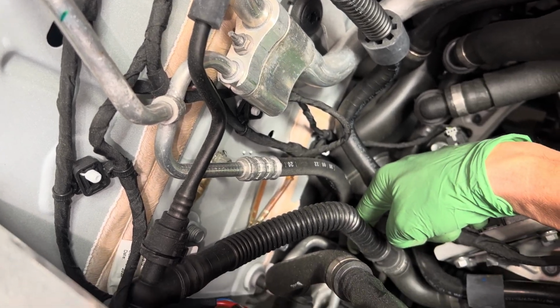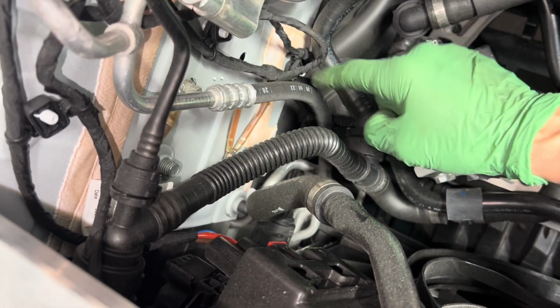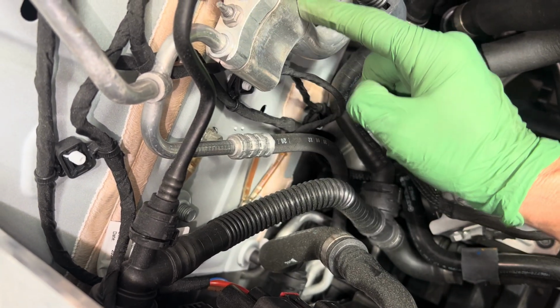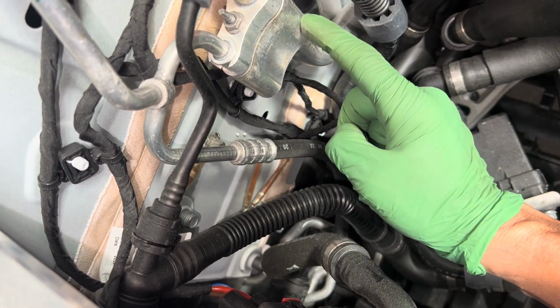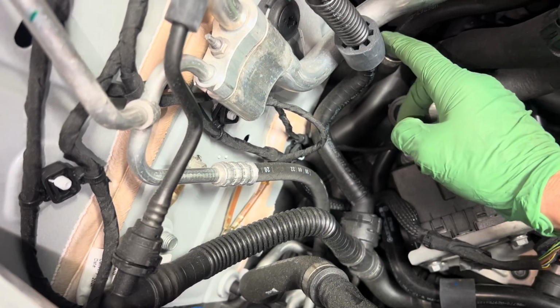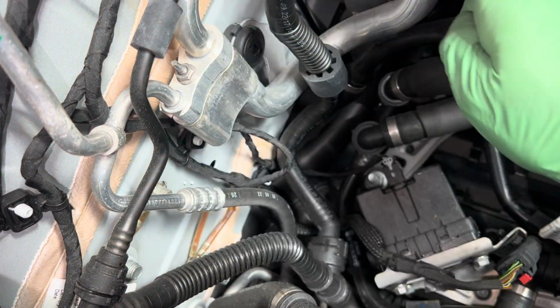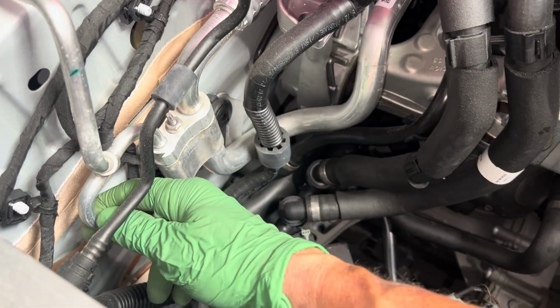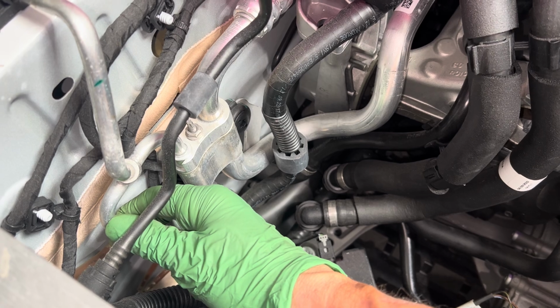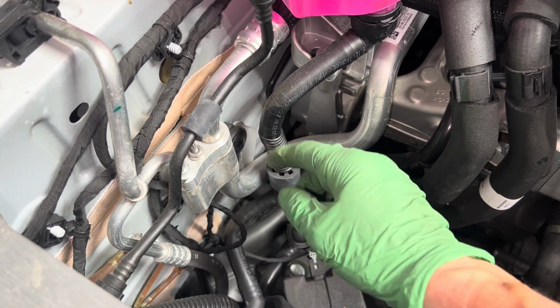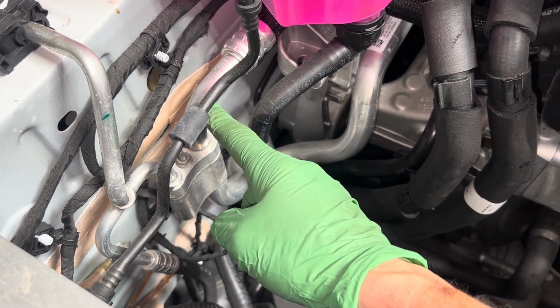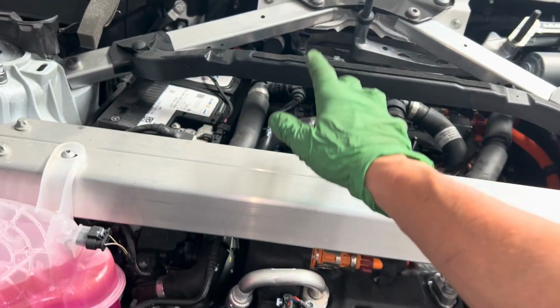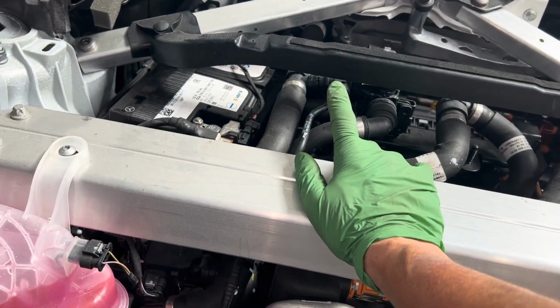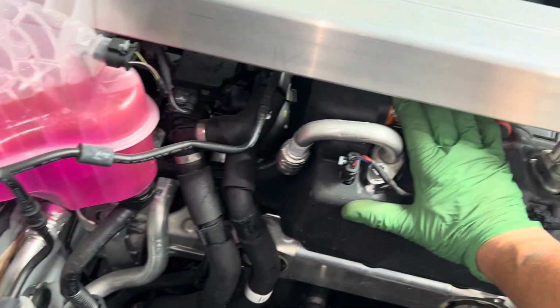So it's coming out as a liquid from the condenser. It goes through this block, into internal passages that travel on the outside, and as this cold suction line returns refrigerant back to the compressor, the excessive heat in this liquid refrigerant is picked up and absorbed by the refrigerant left over from the evaporator. The evaporator cools you, but the evaporator also has to cool the compressor.